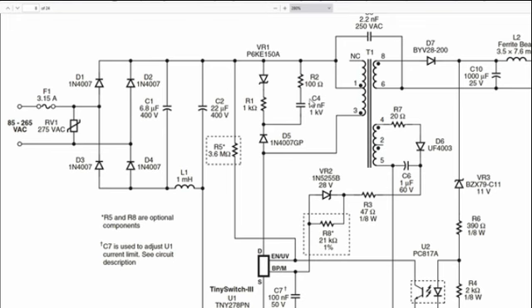It says on the back of the product 230 volts AC. We know it's much higher than that most of the time, so straight away this product has a specification issue. Leave a comment down below, but obviously the UK mains specification has been set to 230, when the product should really have the maximum range of minimum and maximum voltages it can stand, because UK mains, generally most households, is quite often 245, 250, sometimes 260.